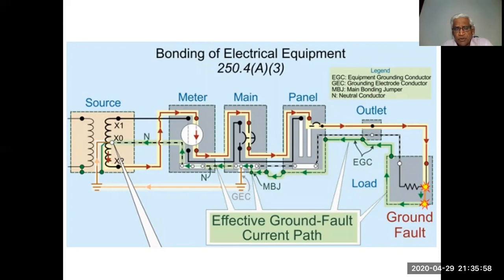On the left side is the source we have. From the source, there is a neutral connected to the earth. From the same neutral, one wire is extended and connected to all the metallic bodies of the meter, main panel, and the outlet, and to the ground fault. In case there is a ground fault coming in the load, the ground fault return path is supposed to be a low impedance path, so heavy current will flow through that, and the circuit breaker trips open or the fuses open.